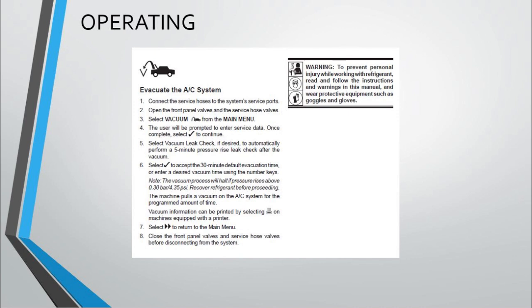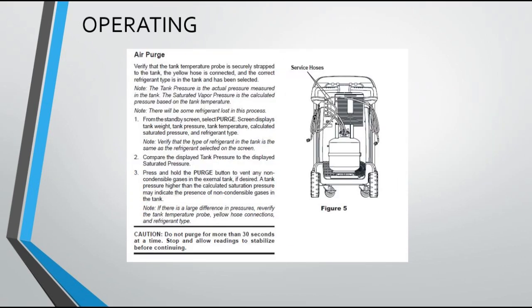Recover refrigerant before proceeding. The machine pulls a vacuum on the AC system for the programmed amount of time. Vacuum information can be printed by selecting on machines equipped with a printer. 7. Select to return to the main menu. 8. Close the front panel valves and service hose valves before disconnecting from the system.